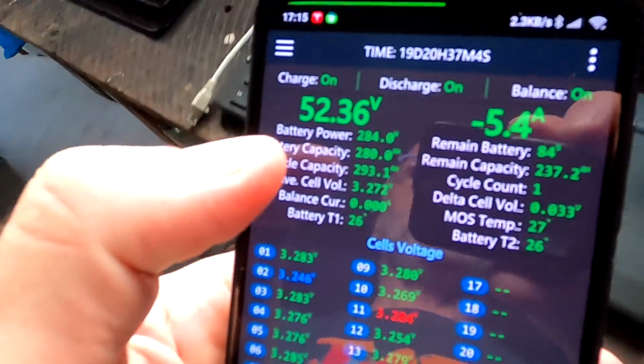Does it matter if we discharge only one battery and not the other, and then parallel them again? No, it doesn't matter at all. I've done some testing, totally crazy testing, I'll show you in a future video very soon. I almost discharged one battery while the other was like 60-70% full, and I paralleled them and there was no issue at all, no currents flowing between the battery banks, nothing. Because lithium iron phosphate is only one voltage, right? Only at the very bottom and very top of the charge and discharge curve will we see balanced currents going from one bank into another. But in between, there's no problem at all. Anytime you can just turn them on in parallel and they will always work.